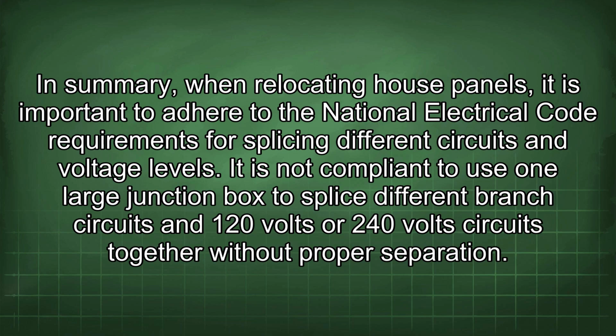In summary, when relocating house panels, it is important to adhere to the National Electrical Code requirements for splicing different circuits and voltage levels. It is not compliant to use one large junction box to splice different branch circuits and 120 volt or 240 volt circuits together without proper separation.